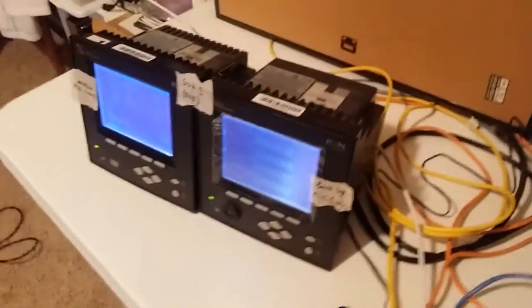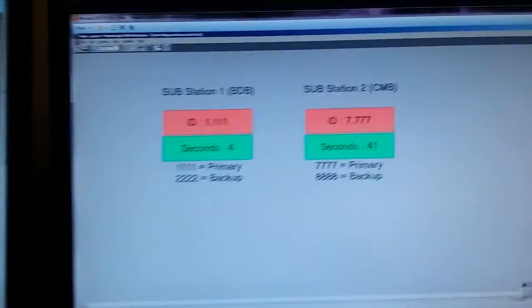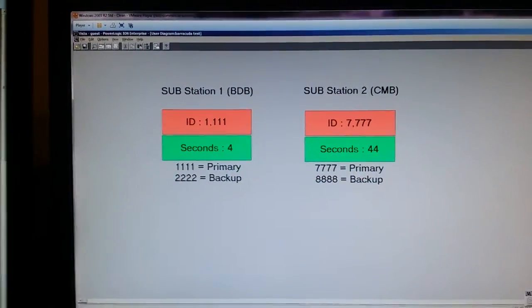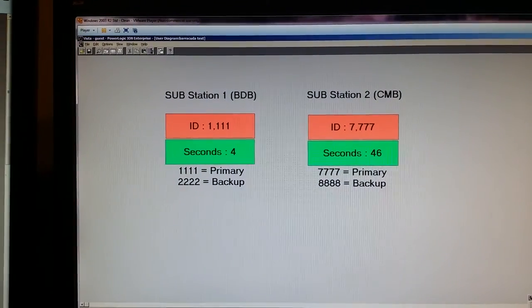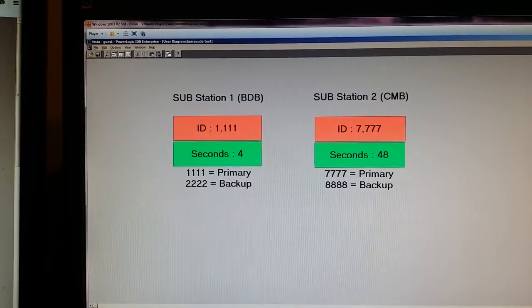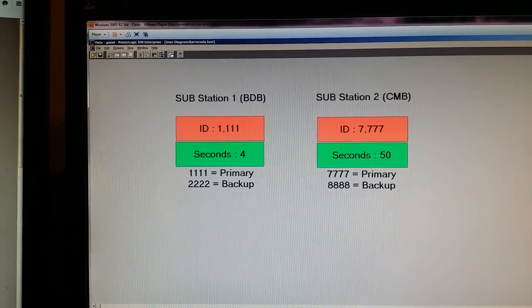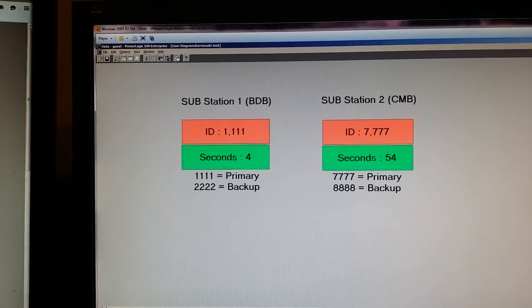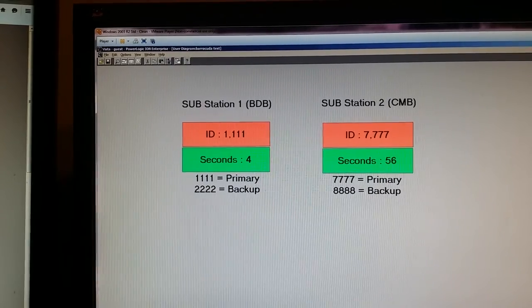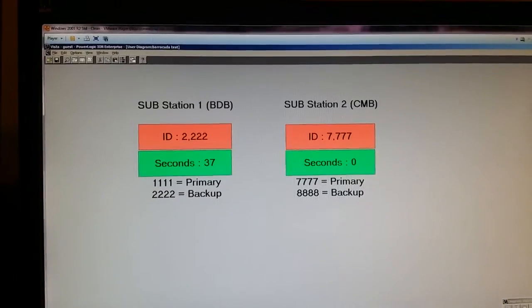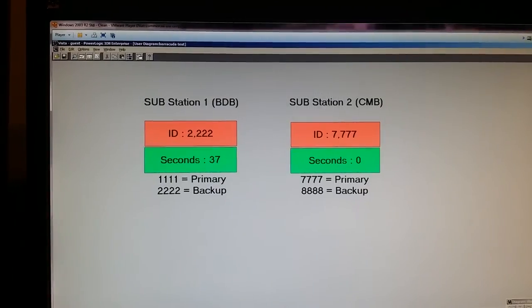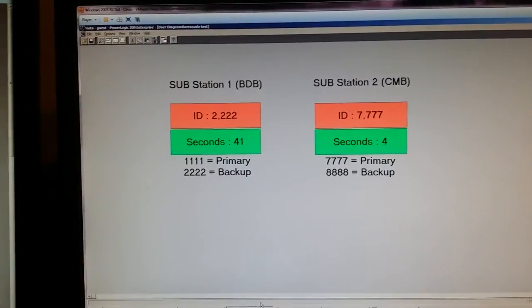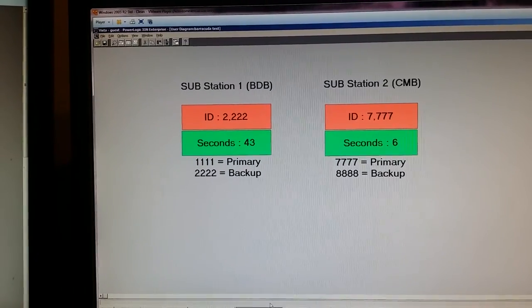We're going to go over here and simulate a comms failure on the primary PLC by unplugging it. Then we're going to go back over here and see what happens. It usually takes between 10 and 15 seconds. There it went. We now switch over to the backup server.